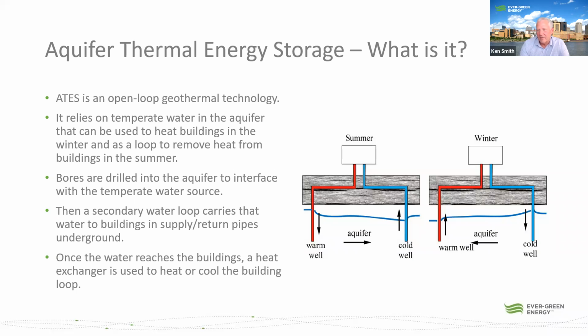Similar here, when you're in cooling mode, you have heat that's going to be rejected, and that heat then would be stored in the aquifer. In the wintertime, you just go the opposite way. I take the warm water out of the aquifer, run it through the heat pump, lift it up to my operating temperature, and I am producing waste cooling. I put that down into the aquifer, and I use that in cooling season.